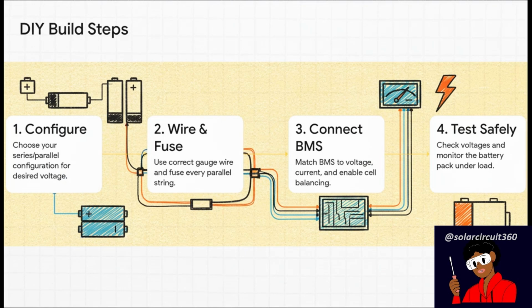So if you're thinking, yeah, I'm going the DIY route, then you need to treat these 4 steps as non-negotiable. First, you figure out your configuration to hit your target voltage, like 48 volts. Second, you wire it all up using the right size wires and, this is huge, you put a fuse on every single parallel string for protection.